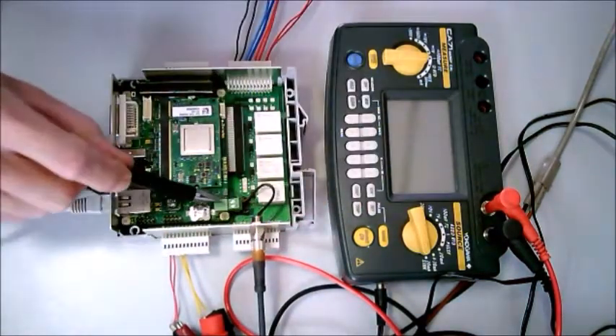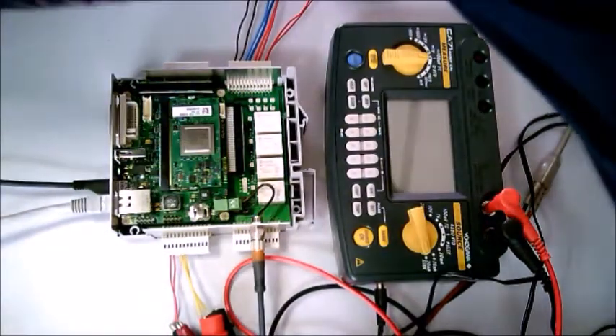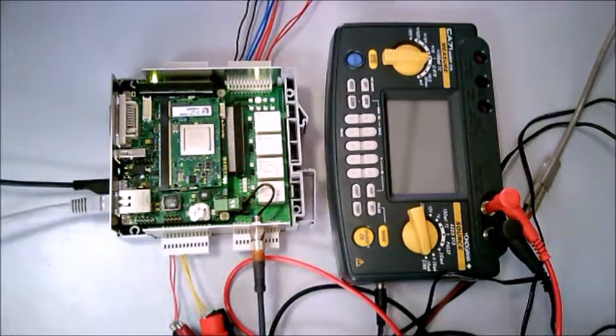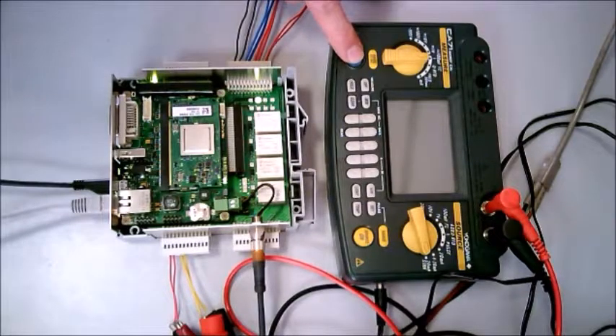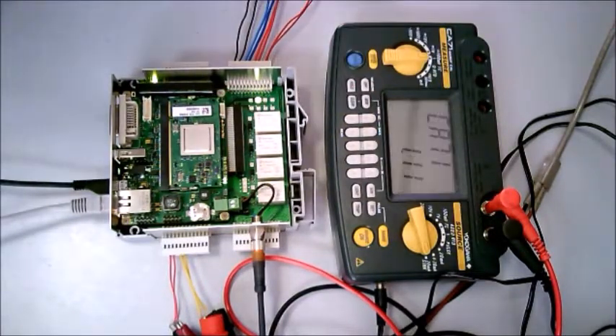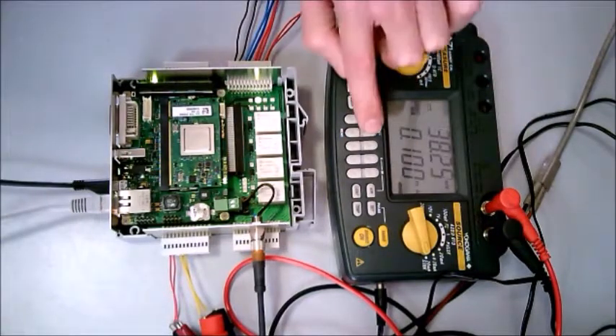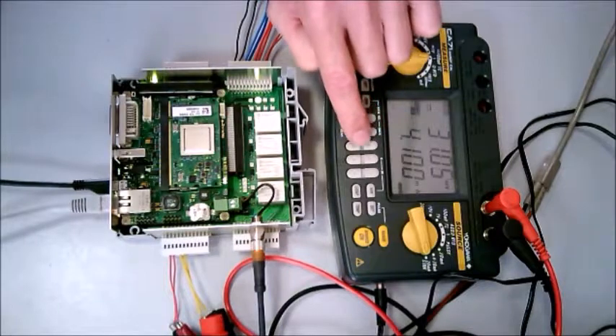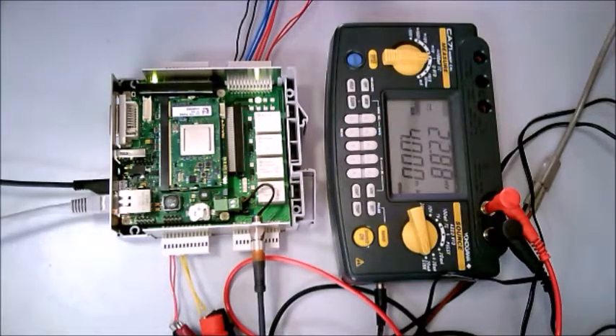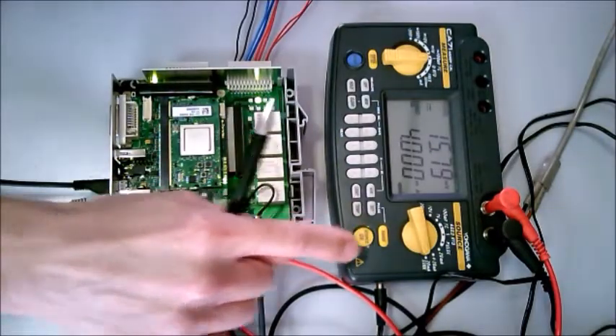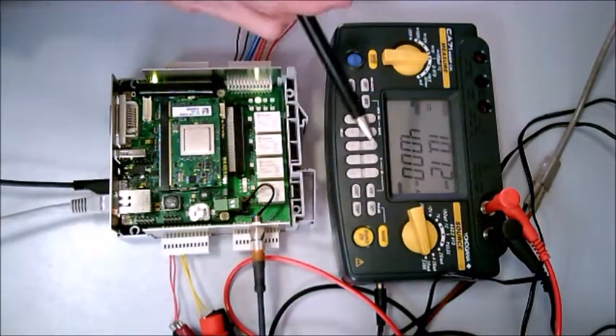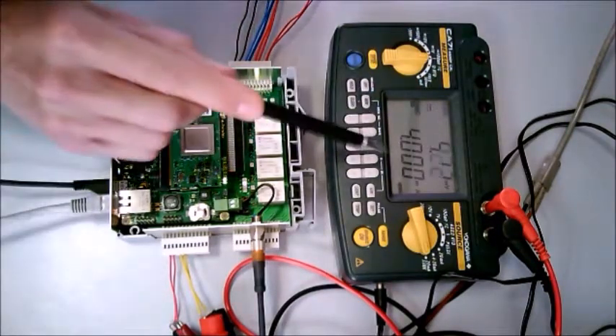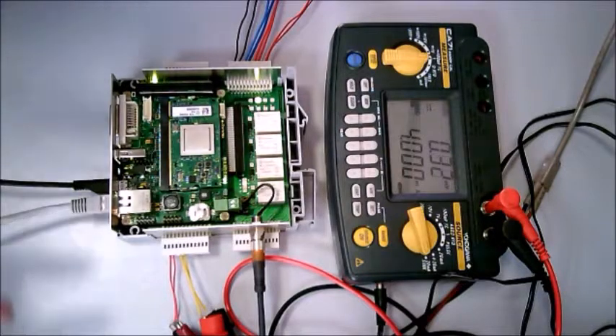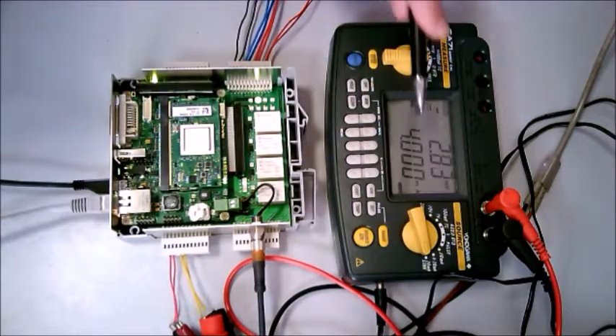That's everything we need. We insert again the power supply connector and we switch on the unit. That's everything we need for starting the testing. Once we have connected the unit, we have to switch on the calibration multimeter generator. Okay, and if we activate the generation of the signal, we will have an input, an active input of this generated value.